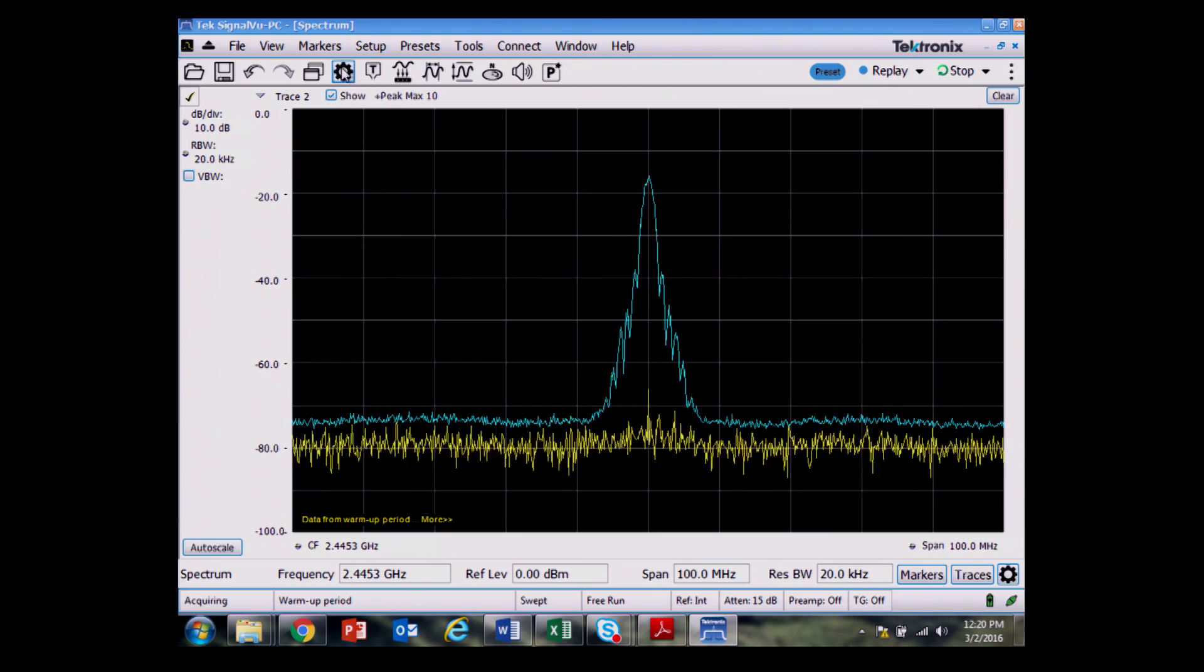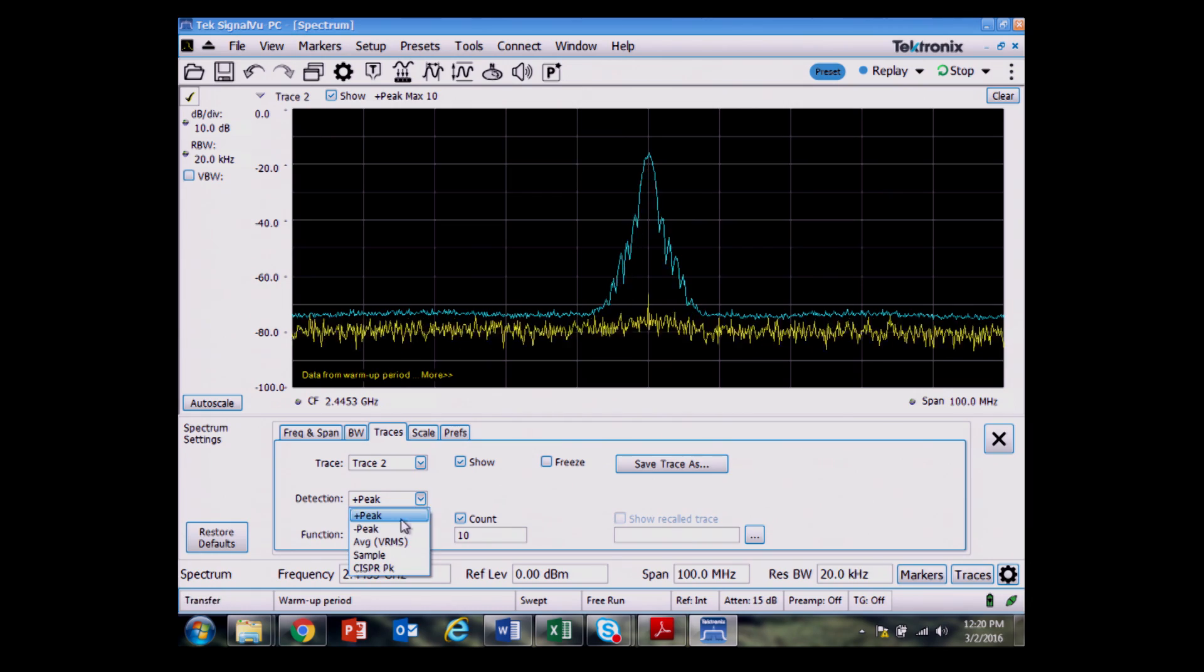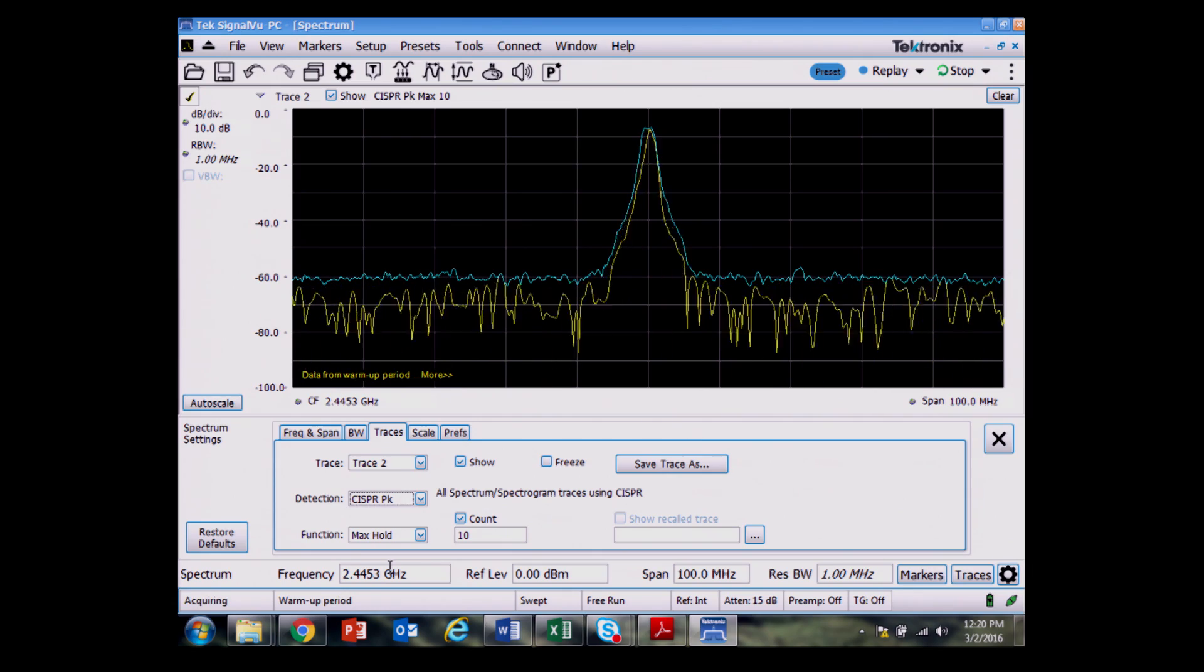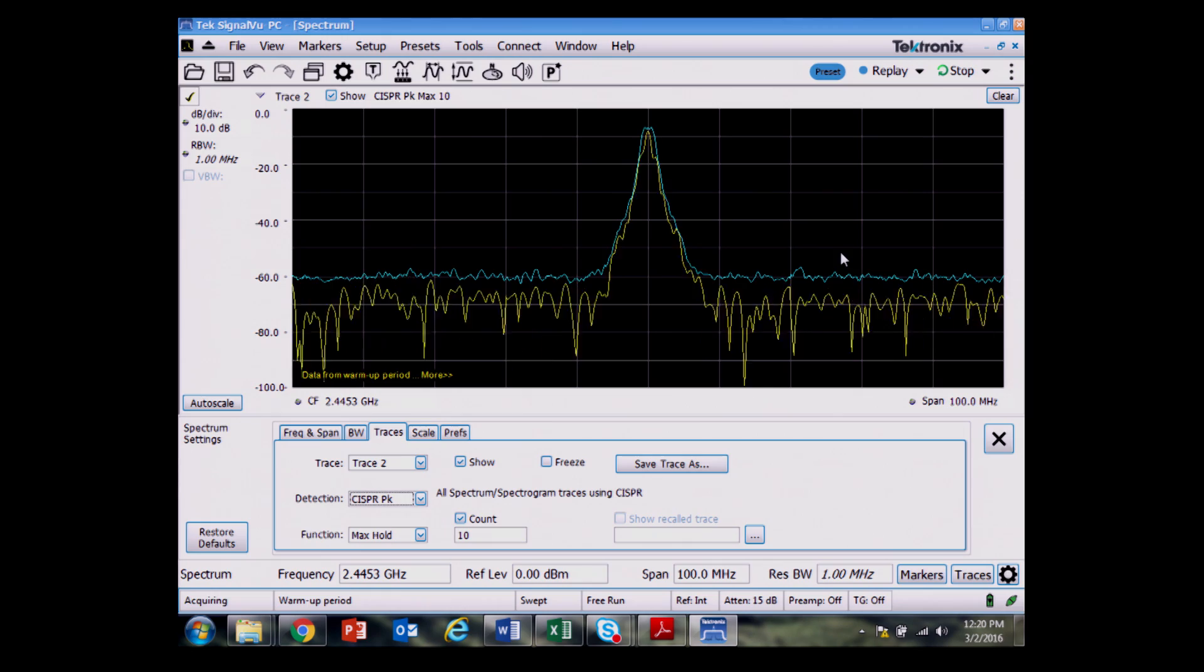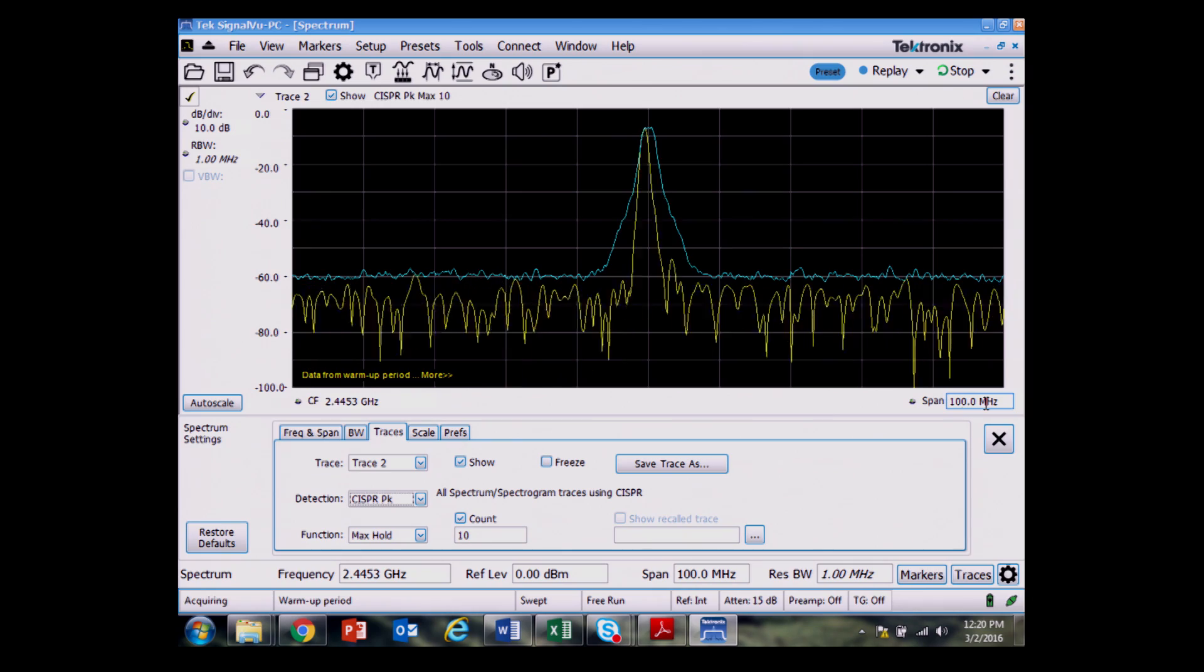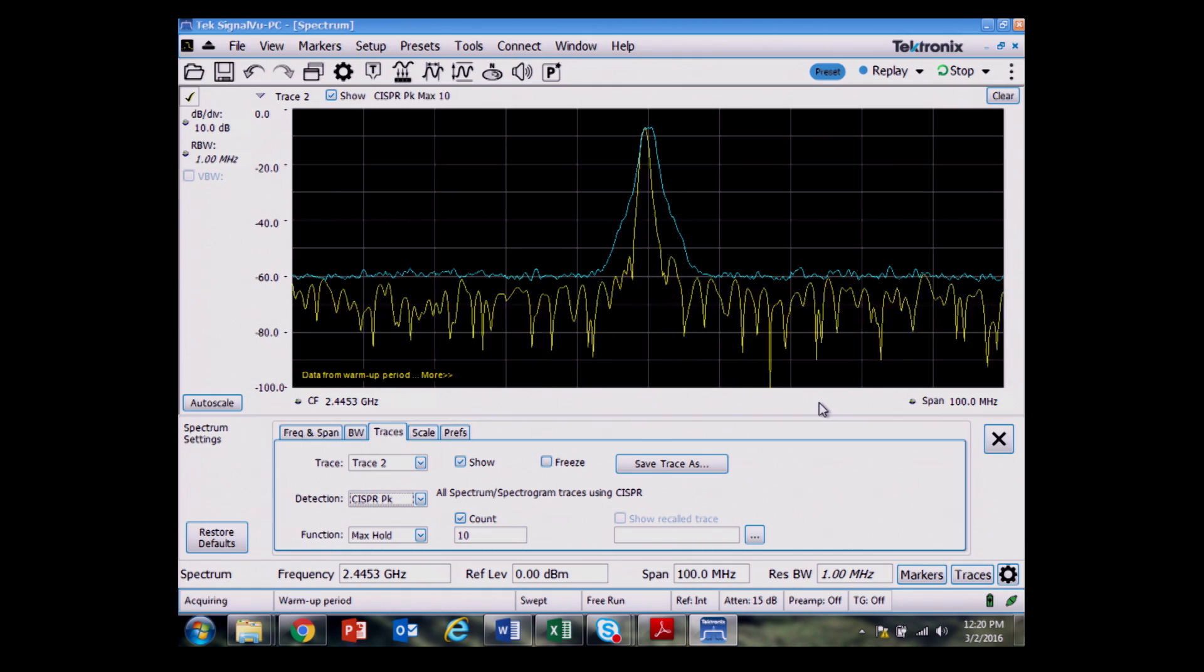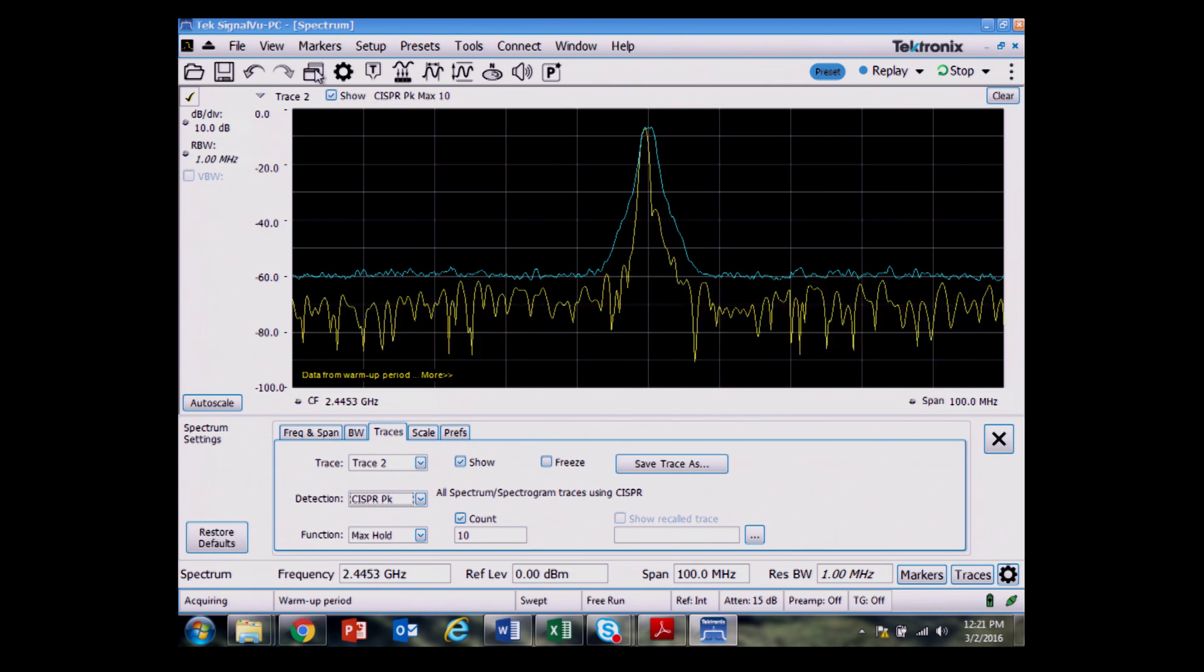If I go to the settings and for traces, I do have a CISPR peak detector, which is a worst case detector. As long as I pass the limit lines here, I know that I'll be compliant to the EMI standards. I'm just looking close into the band. Not really the way that you'd use it, but that feature's available for some EMI checks.